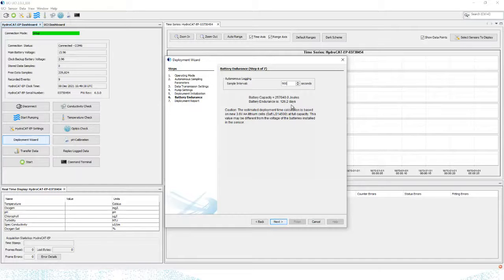Note that this calculation is based on a full battery pack, so if you have used batteries in this, your UCI is not going to know that. It doesn't know that the battery pack does not have full capacity, and it also doesn't know if you're applying external power to the instrument. It's just assuming you're using a brand new set of batteries here, so keep that in mind.